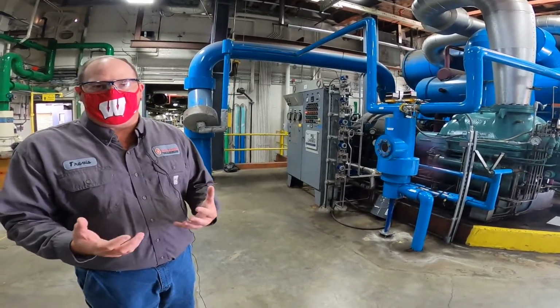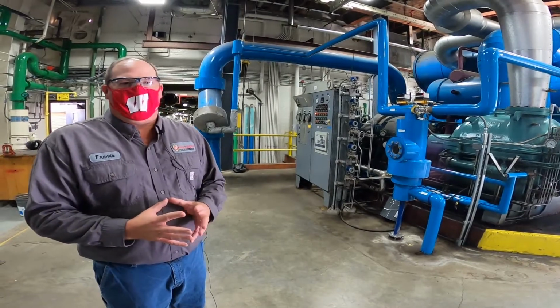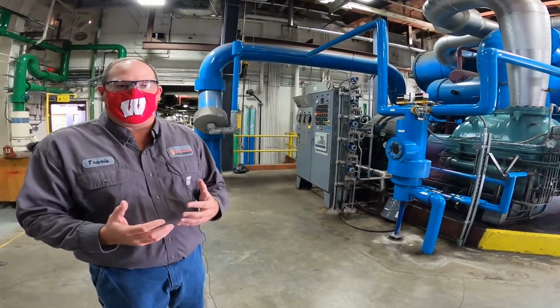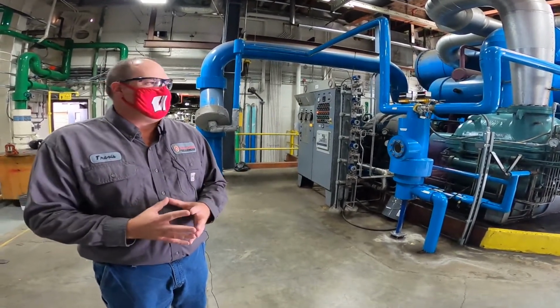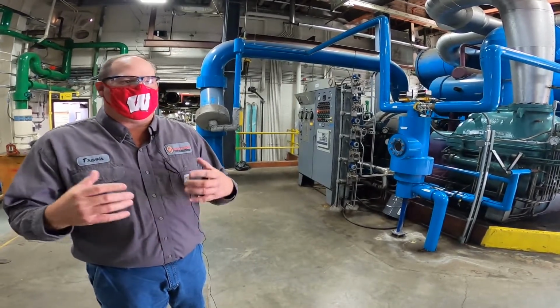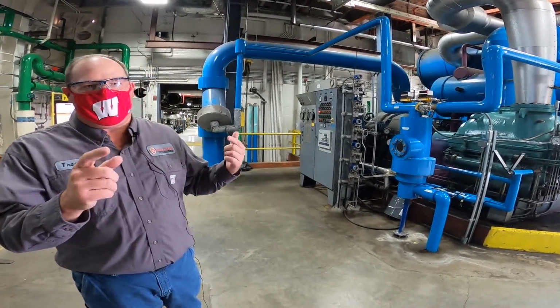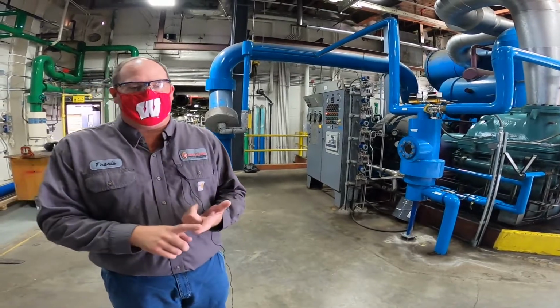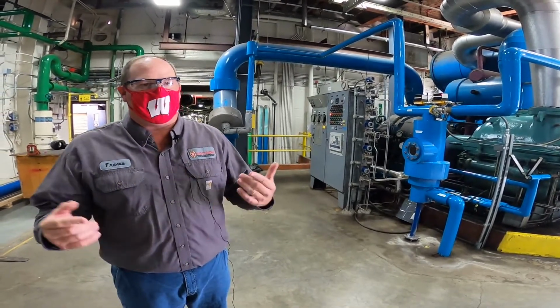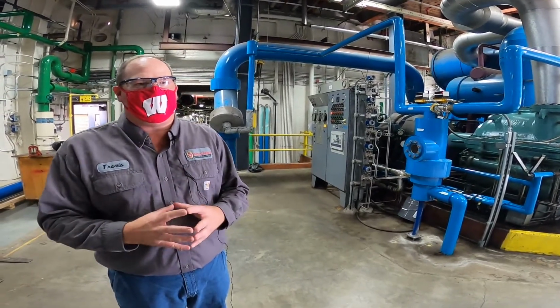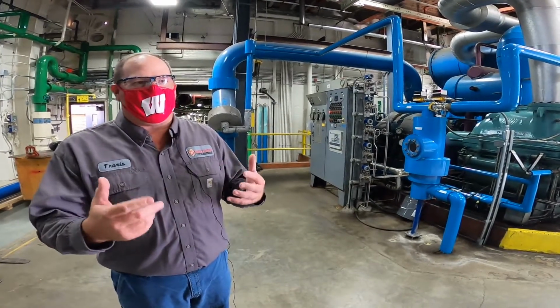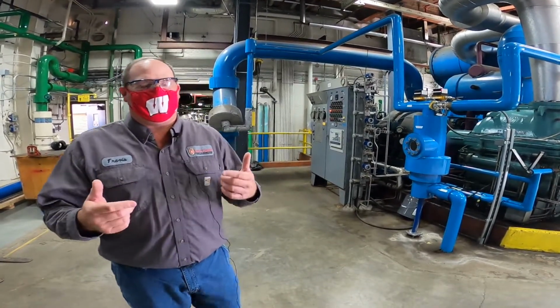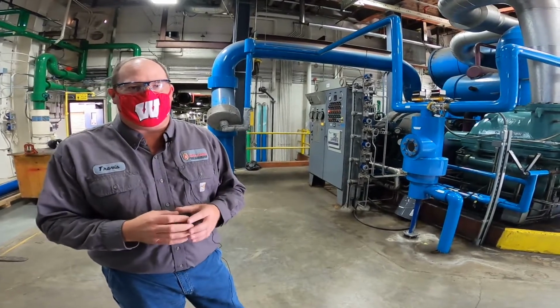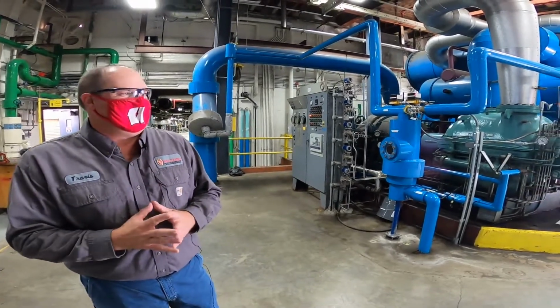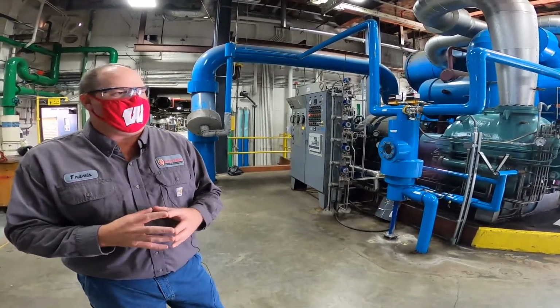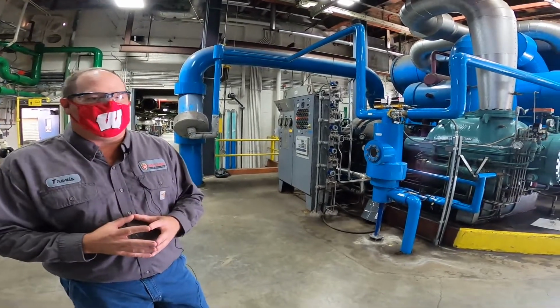Campus has become more efficient over the years. At one point, we thought we were going to have to install quite a few more chillers. It doesn't look like we will unless we switch the Freon at the Charter Street plant from R22 to 134A. Then we're going to lose 25% capacity because there's not a Freon right now that is as efficient for these machines as R22. There's no replacement Freon that we can utilize without dropping load.